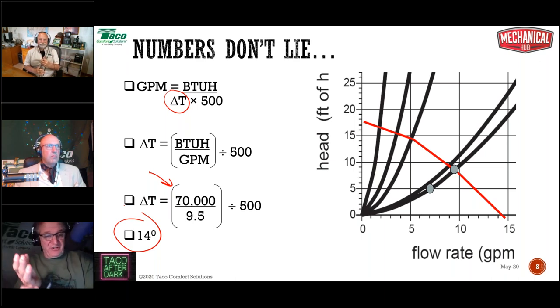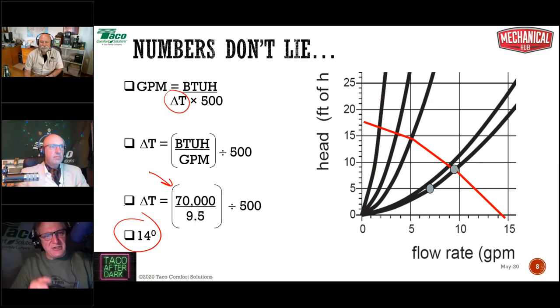We haven't done a little fudge factor with the heat loss, like that never happens. We haven't had any fudge factor with the actual installation of the heating elements. Oh, like that never happens. Or maybe the heating elements have been perfectly designed and installed according to the heat loss, which has 15% of fudge factor built in it already.